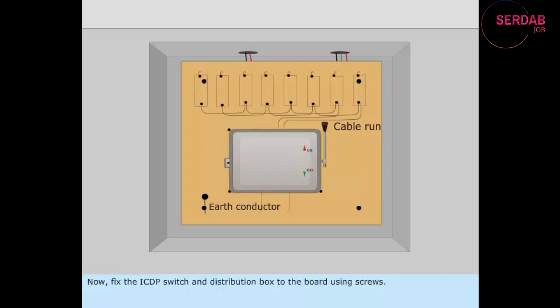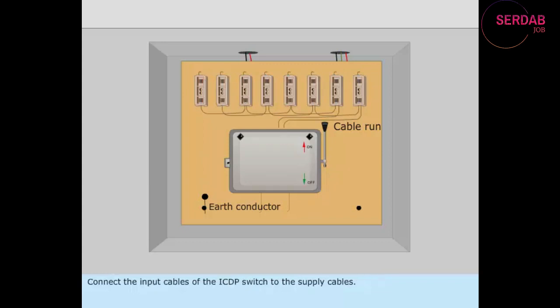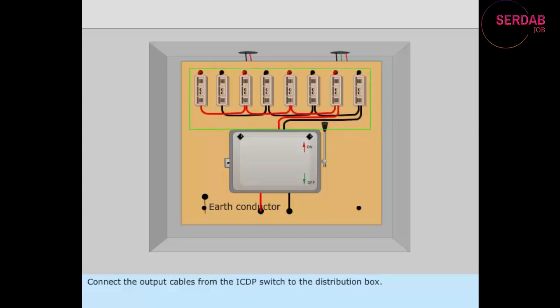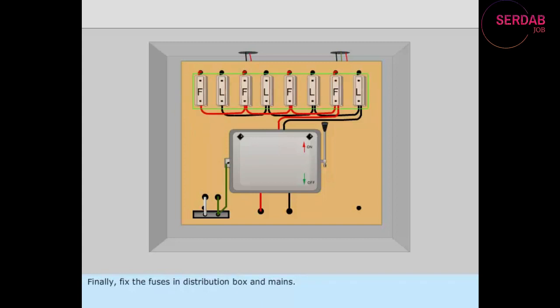Now, fix the ICDP switch and distribution box to the board using screws. Connect the input cables of the ICDP switch to the supply cables. Connect the output cables from the ICDP switch to the distribution box. Earth the body of ICDP switch and distribution box by suitable earth wires. Finally, fix the fuses in distribution box and mains.